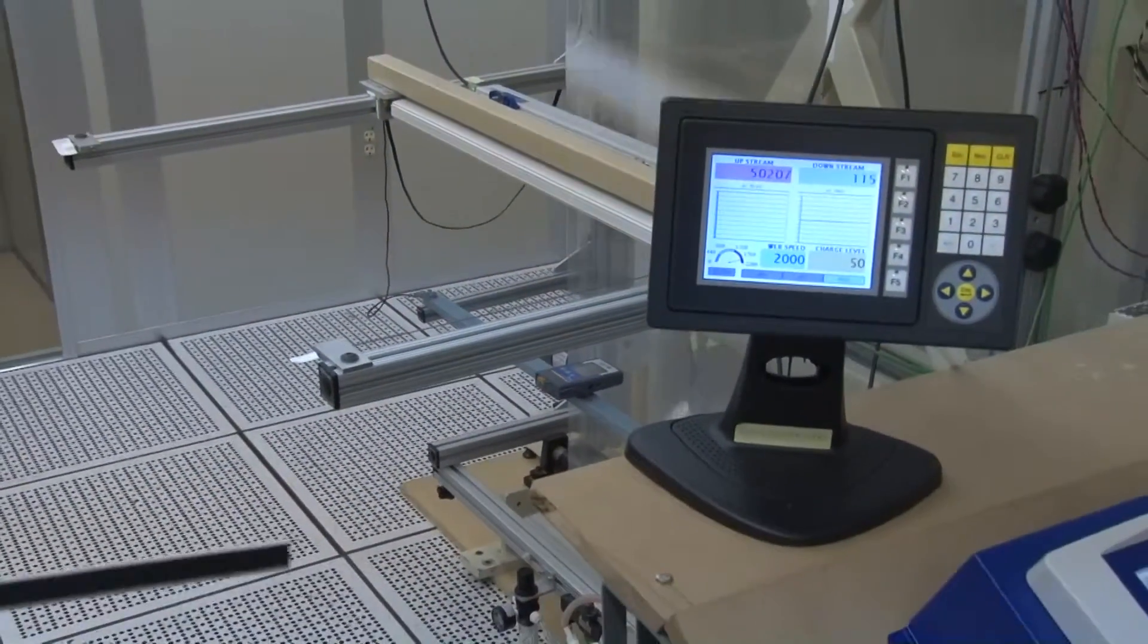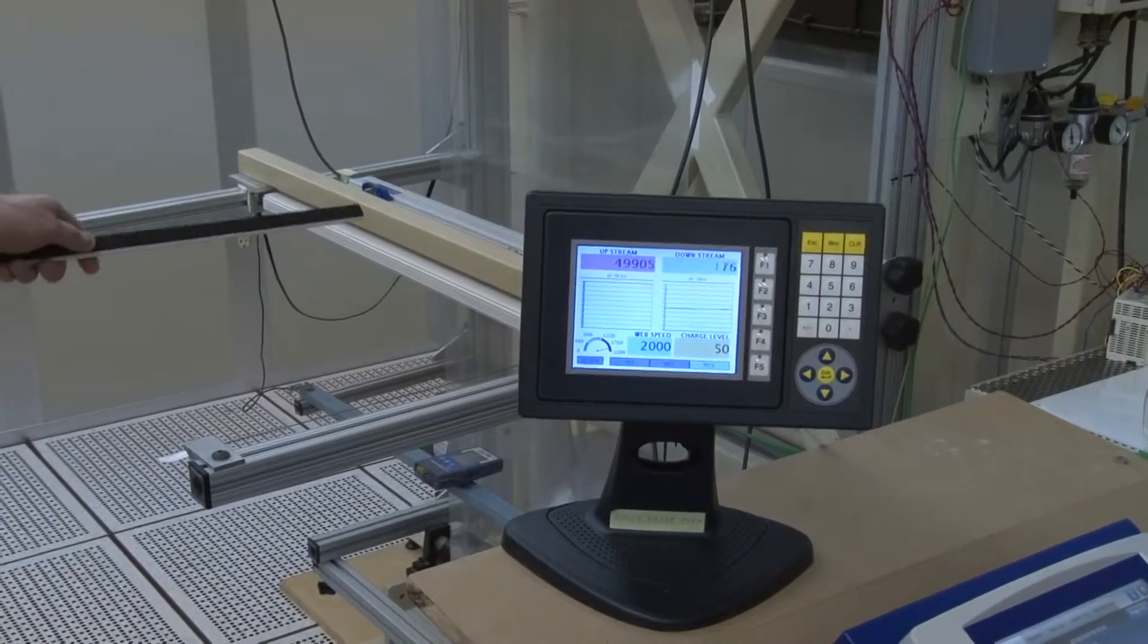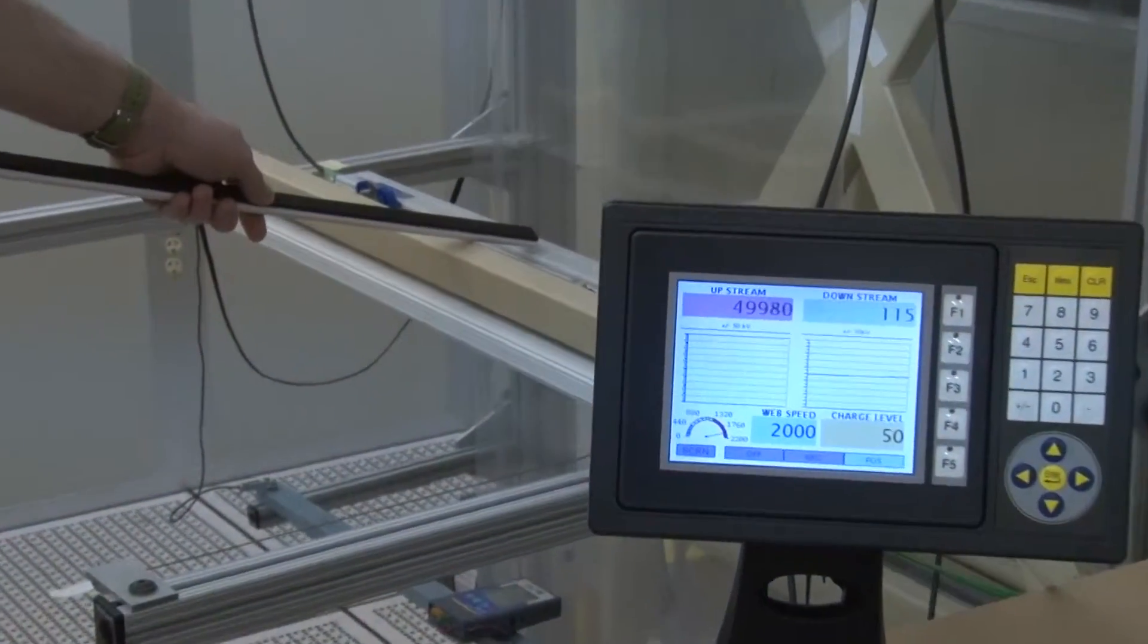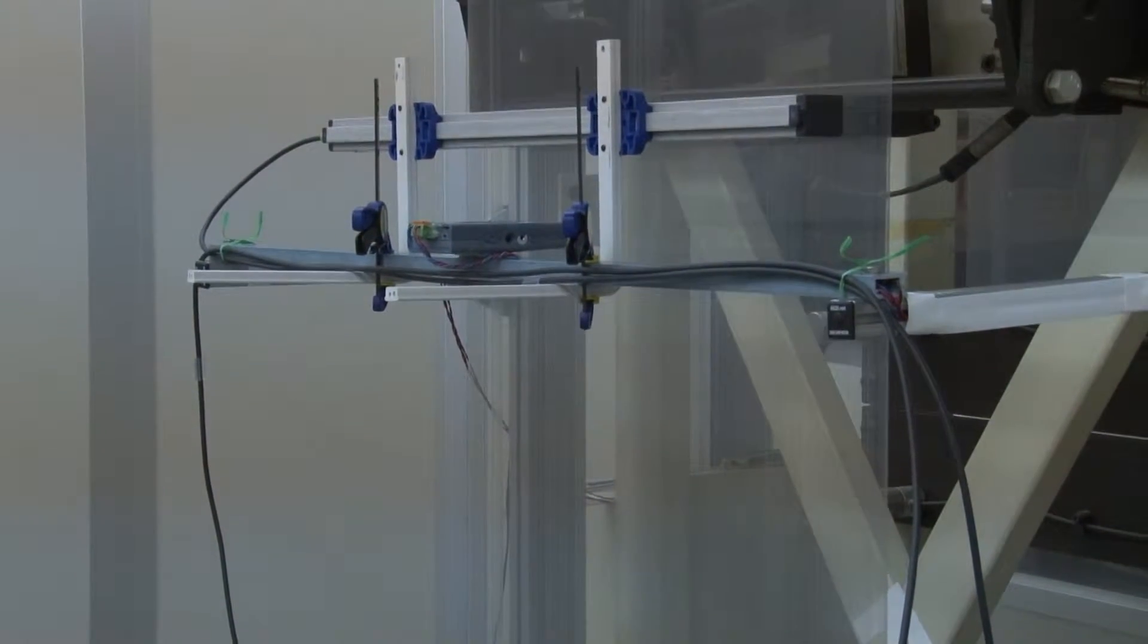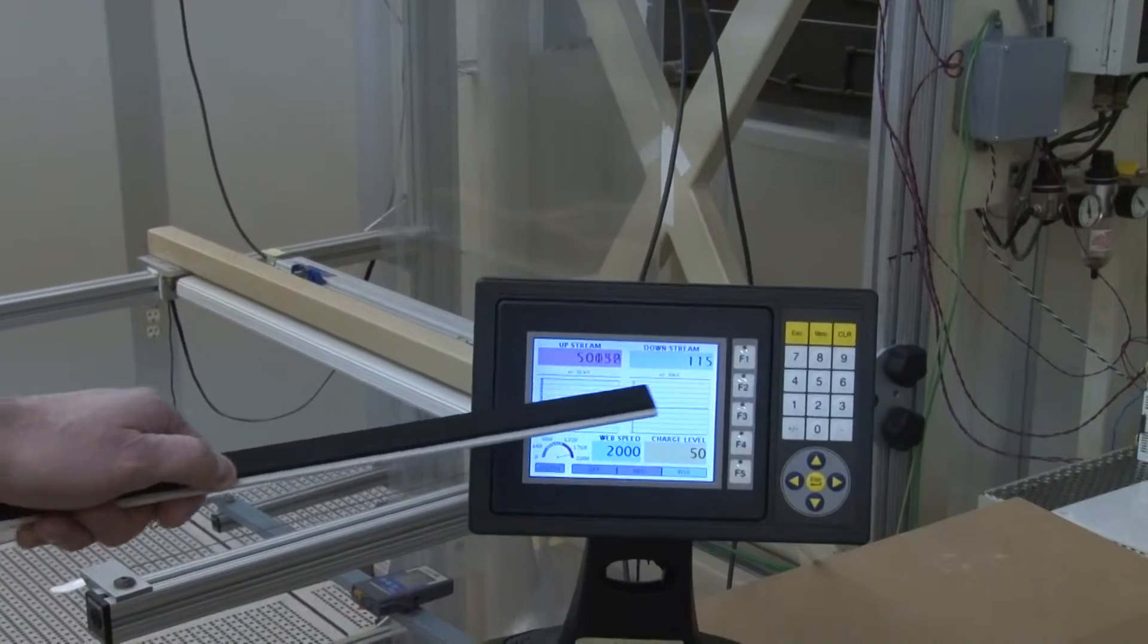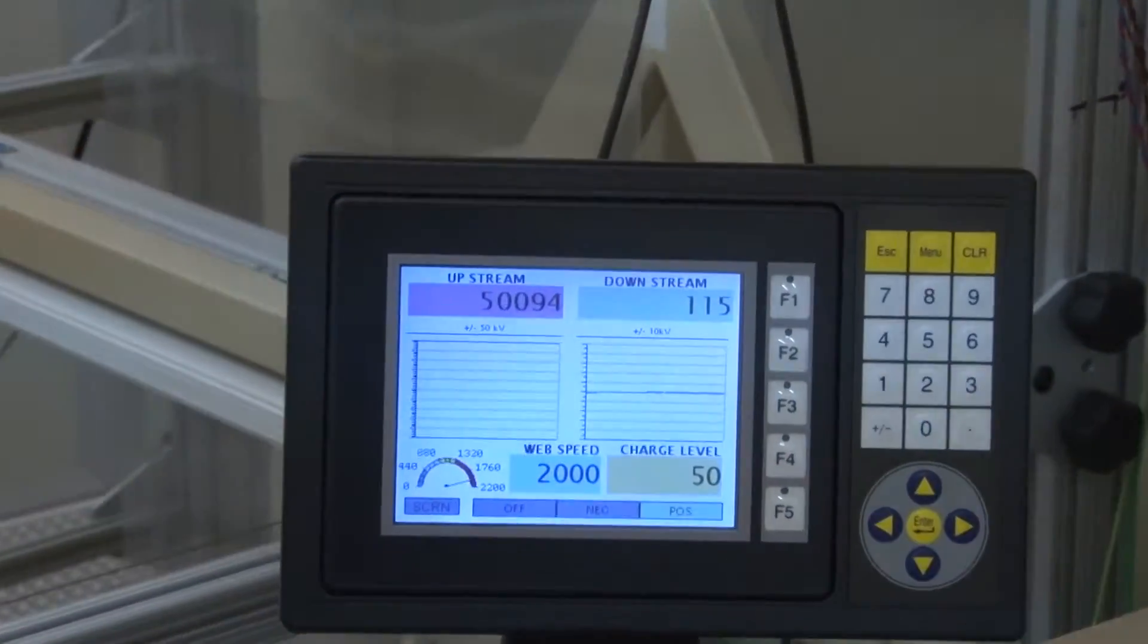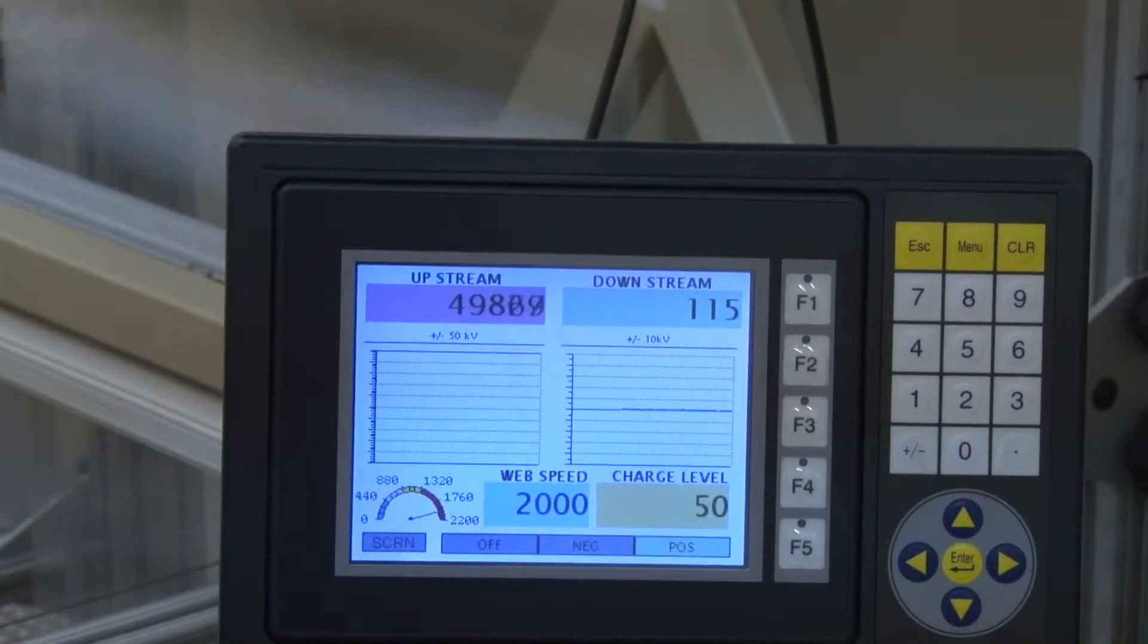As we go downstream sensor, which is downstream from the neutralizing bar, on this sensor we can see how well the material has been neutralized, and in this case we're taking 50,000 volts down to 115 volts, which is essentially zero in this type of application.